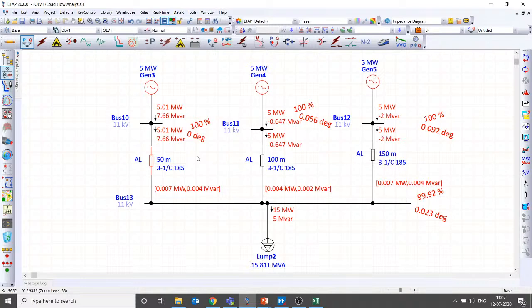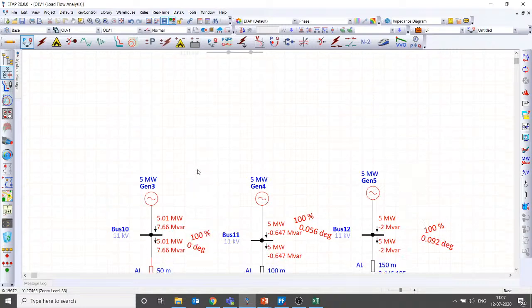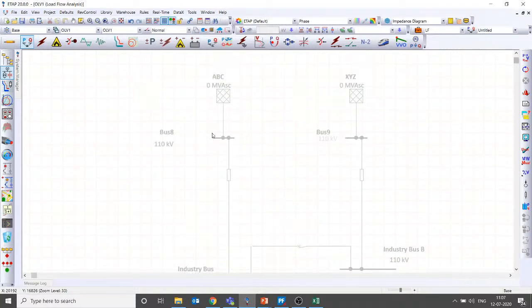Is it possible to get slack bus voltage and angle if I have the details of three phase and SLG fault current at each slack bus? Answer is no. Sasikumar, your question is, if you know three-phase fault current and single line to ground fault current at slack bus, is it possible to find out an angle? Answer is no. There is no relationship between the short circuit strength and the voltage and phase angle.